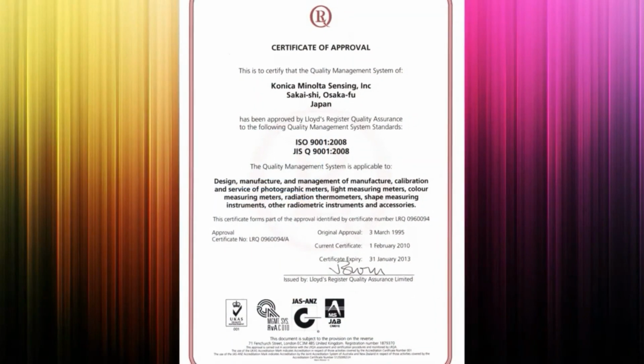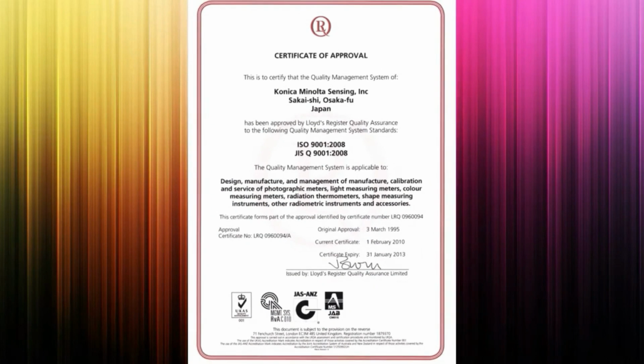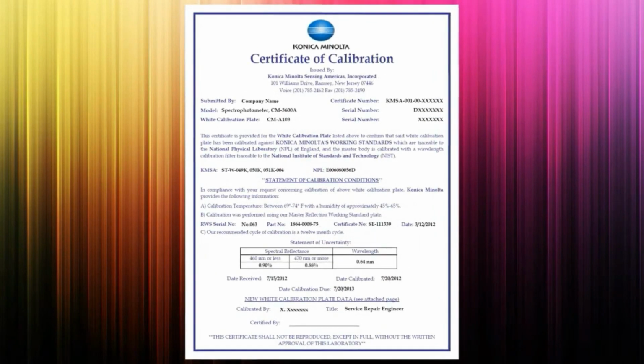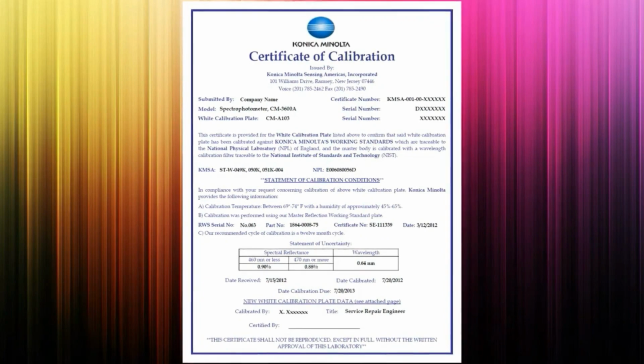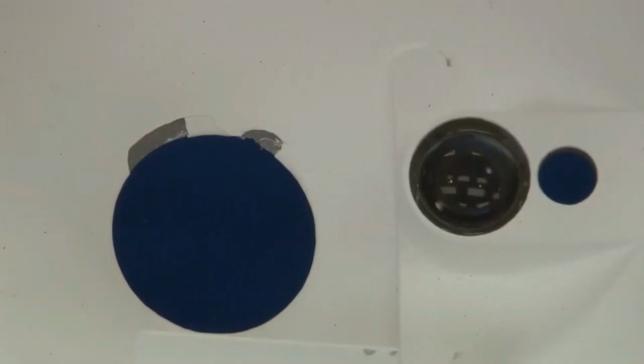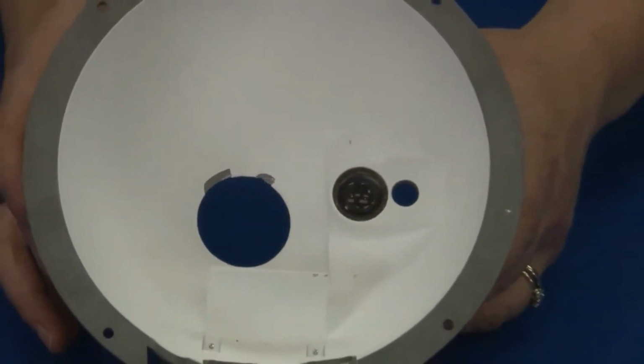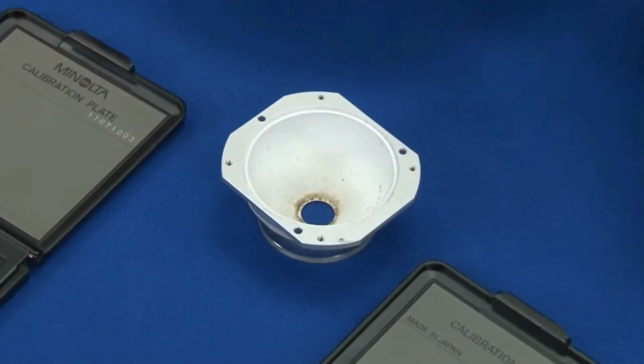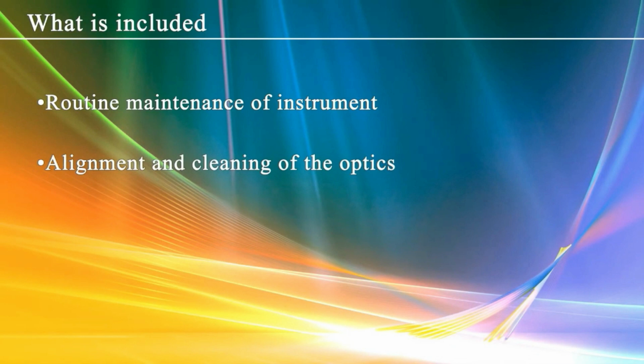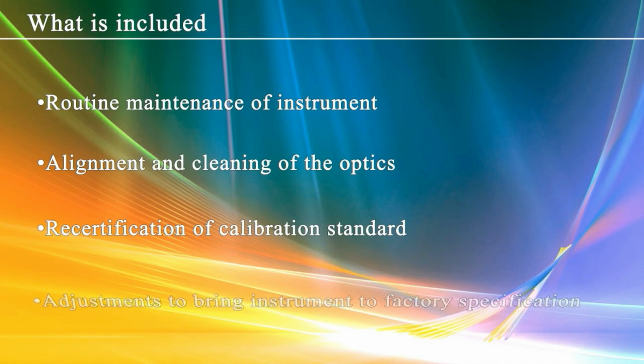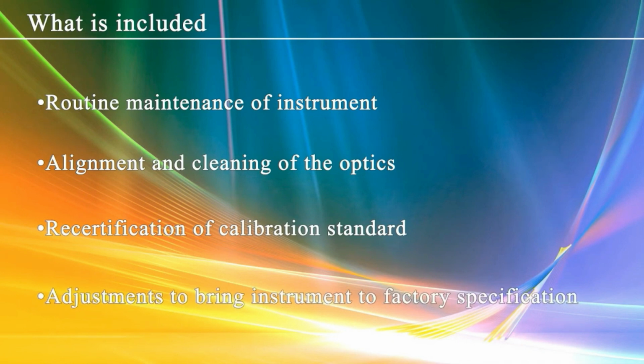This process can provide customers an ISO certificate and provide adjustments to the instrument required due to changes in conditions of the components over time. Certain conditions could affect the readings depending on your environment. Dirt or dust in the optics or sphere, stains or scratches on your white calibration tile are just a few examples of conditions that can affect the readings. Annual calibration includes routine maintenance of the instrument, aligning and cleaning of the optics, recertification of the calibration standard, and multiple adjustments to bring the instrument into factory specifications.